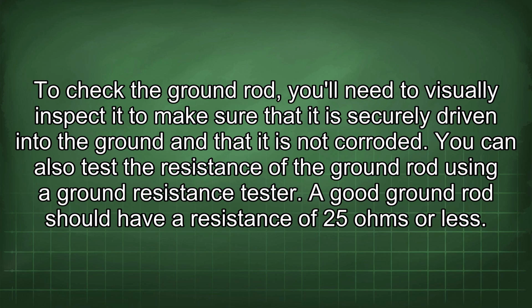To check the ground rod, you'll need to visually inspect it to make sure that it is securely driven into the ground and that it is not corroded. You can also test the resistance of the ground rod using a ground resistance tester. A good ground rod should have a resistance of 25 ohms or less.